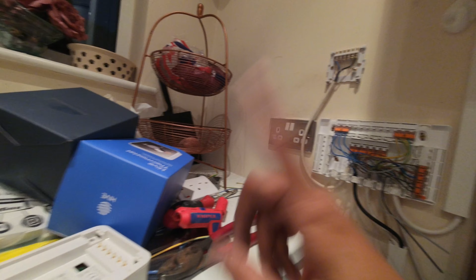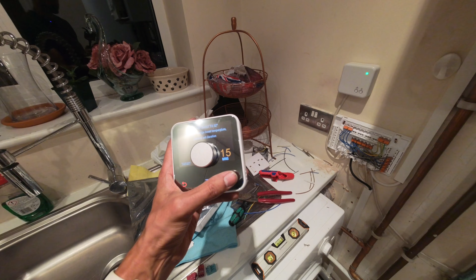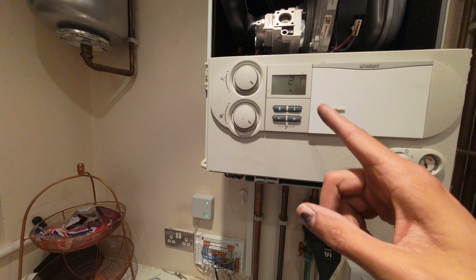Right, we are powered on. Grommet's changed, just in case people doubt me. I've used the grey as a switch live, terminate the black just in there. Boiler is on. This is paired up. So now what we'll do first is, let's boost the heating. So heating, boost that. Alright, that's got demand there, so that should start motoring over, which it is. Wait for the click. Click. Should get a demand on here. But I'm not.